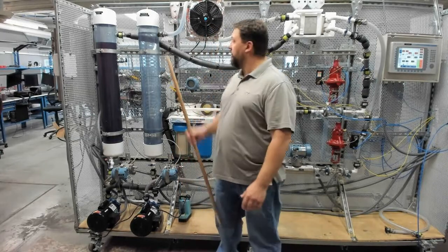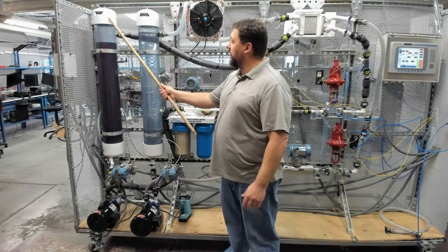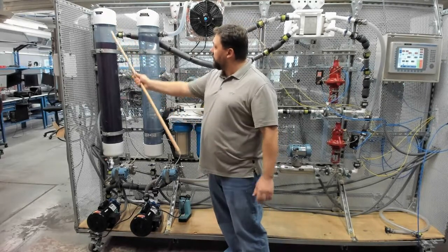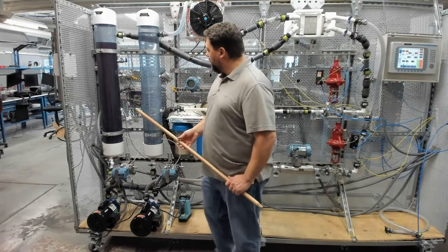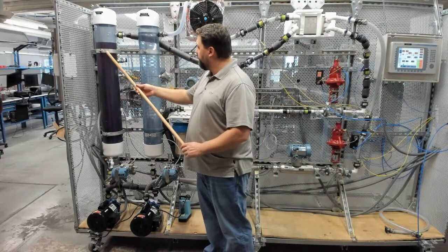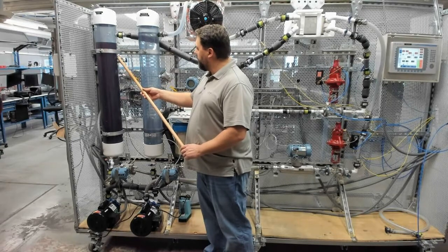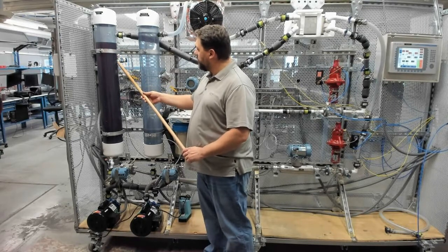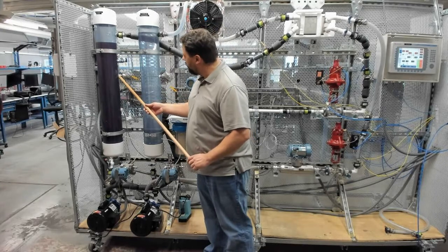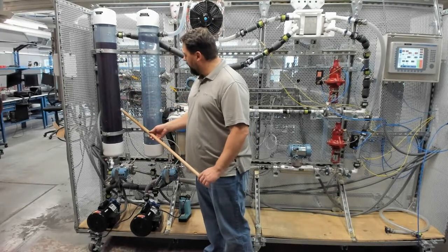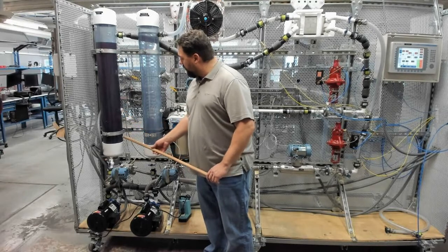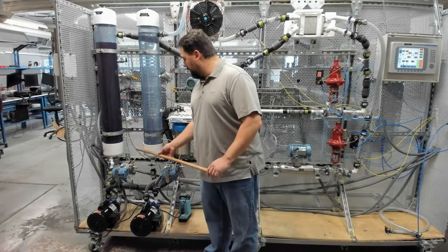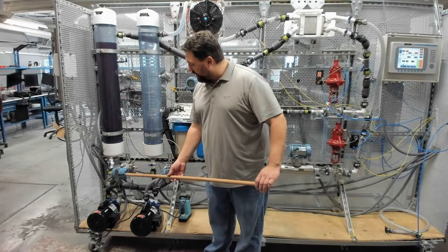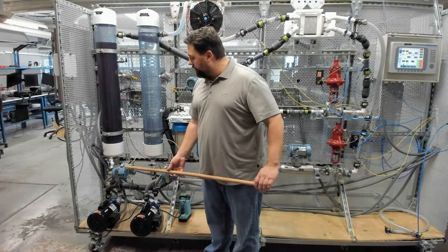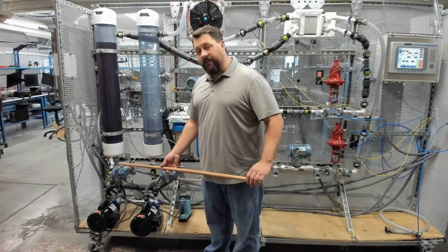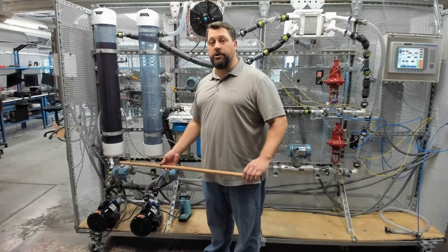So let's start with the heat transfer tank. This is the hot tank, tank A. You can see that there's a purplish color fluid. That's the propylene glycol in there. Right here we have a level switch, a temperature switch, a thermocouple, another level switch, and then we have a tap right here. Now this tap is coming down and comes into this transmitter. This is the level transmitter. This is a differential pressure transmitter that's been configured to measure level. So it's called pressure-based level measurement.